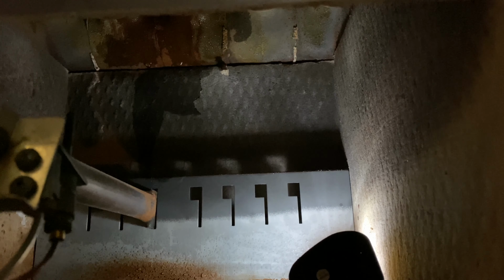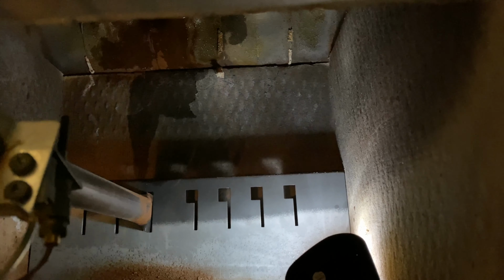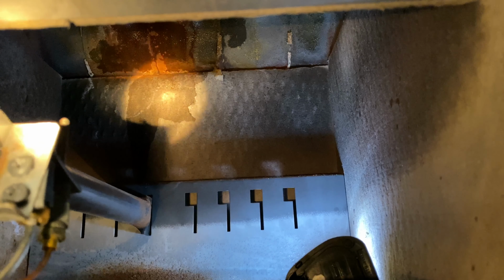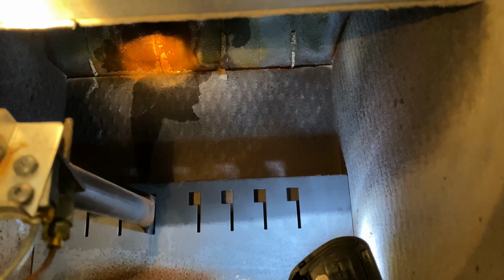To summarize, there are many reasons for why the pilot light may not stay lit. In my case, it was due to a cracked boiler block through which the leaking water kept extinguishing the pilot light. One clue to a leak is that in the distance on the left, you can see rust, which tells you that the leak was probably happening for a while now.